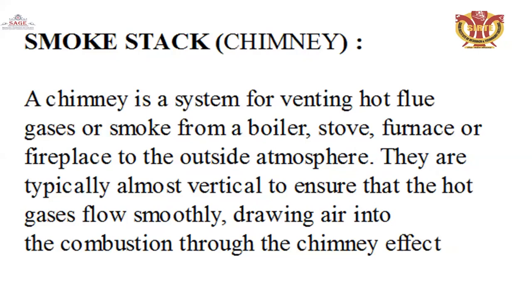The smokestack — also called a chimney — is a system for venting hot flue gases or smoke from a boiler, stove, furnace, or fireplace to the outside atmosphere. Chimneys are typically almost vertical to ensure hot gases flow smoothly, drawing air into the combustion through the chimney effect. The inside atmosphere is hot and the outside is cold; due to this pressure difference, exhaust gases are automatically drawn out to the atmosphere.